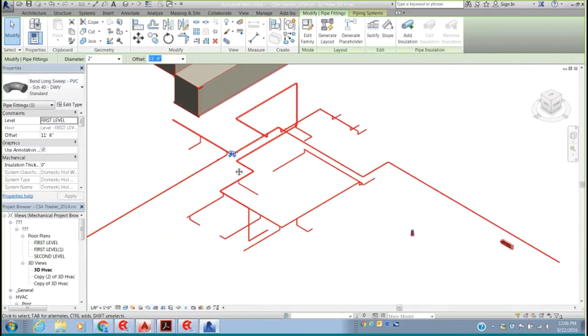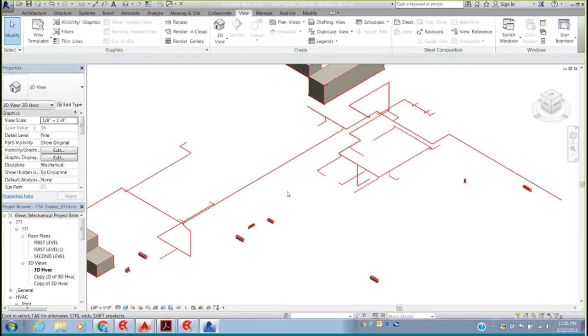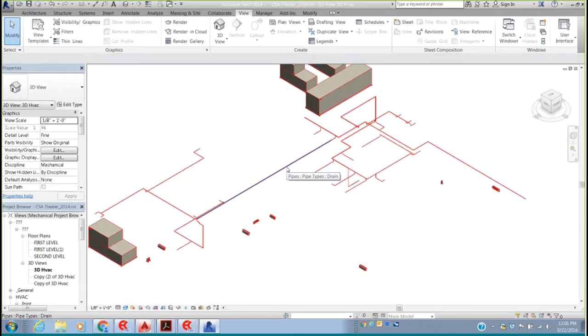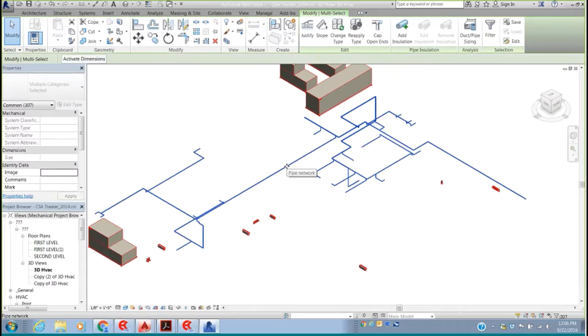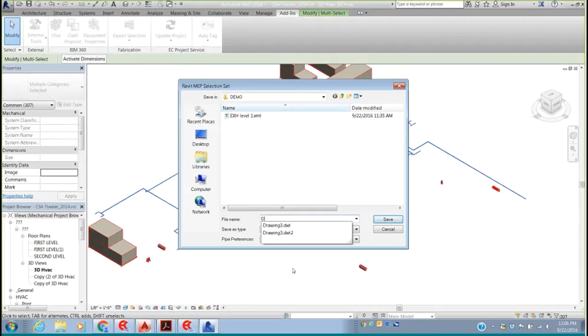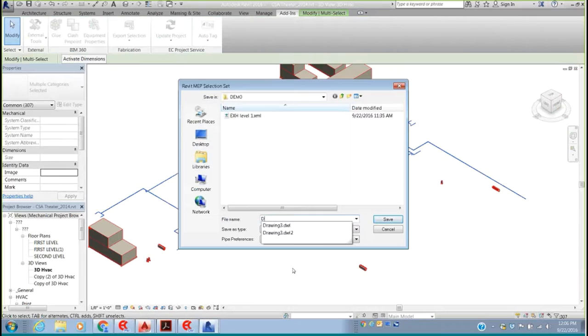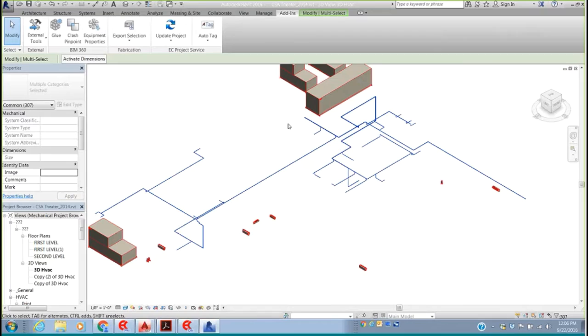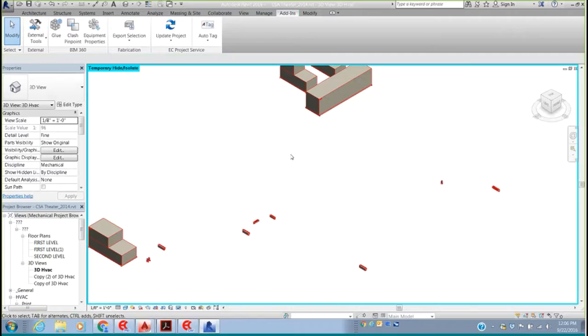To capture the information out of Revit, I put my cursor over the pipe, click the Tab key, and that selects the entire domestic hot water system. Then I go to Add-ins and select Export Selection. I'll name this 'domestic hot water' and save it to a folder on my desktop. Once saved, I can hide that element. If I had additional pipe systems, I can bring them in one at a time and decide what material types to assign in AutoCAD MEP.